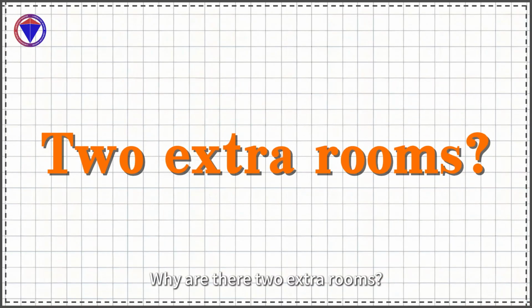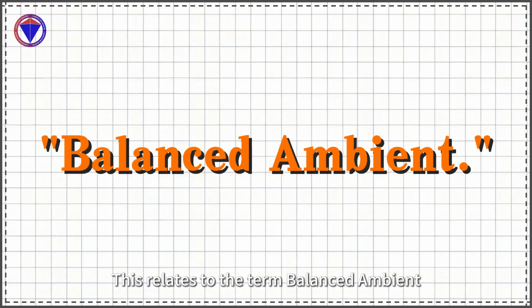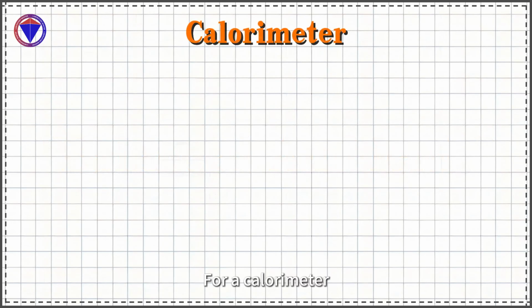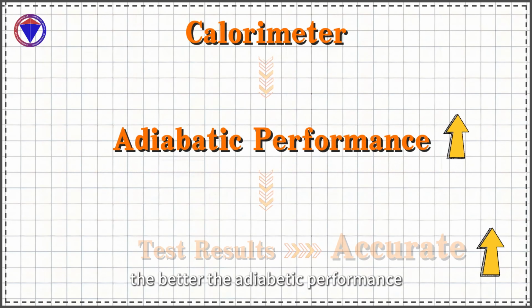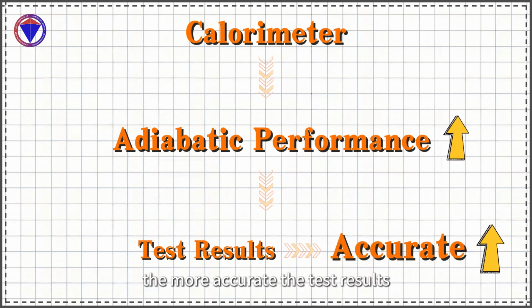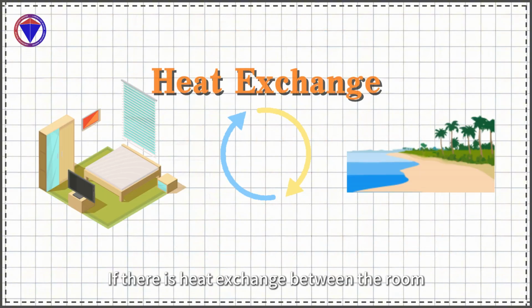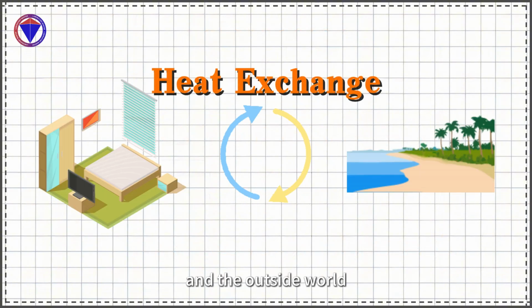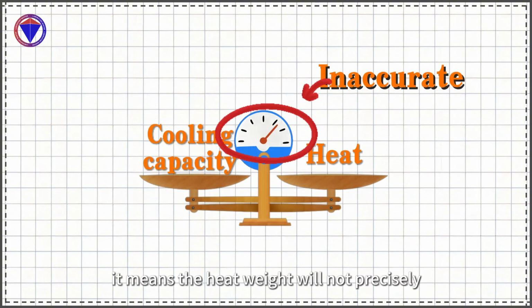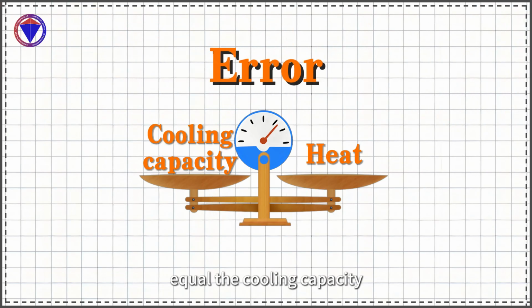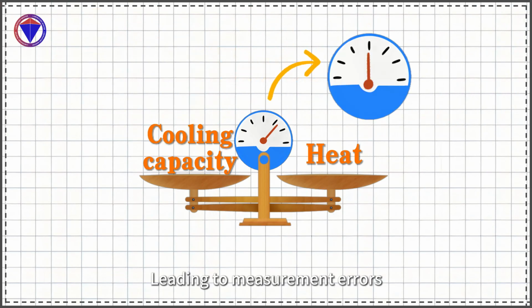Why are there two extra rooms? This relates to the term balanced ambient. For a calorimeter, the better the adiabatic performance, the more accurate the test results. If there is heat exchange between the room and the outside world, it means the heat weight will not precisely equal the cooling capacity, leading to measurement errors.